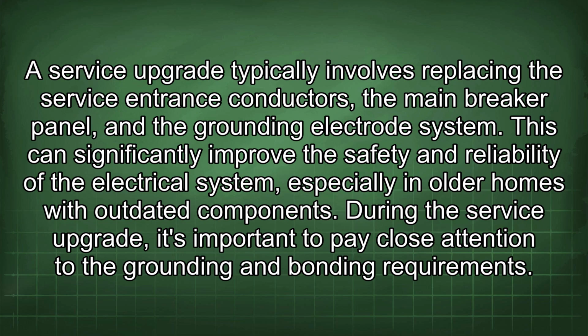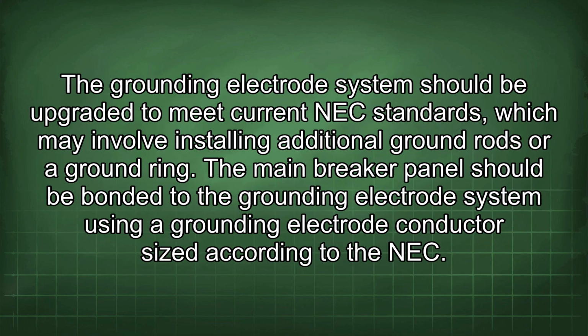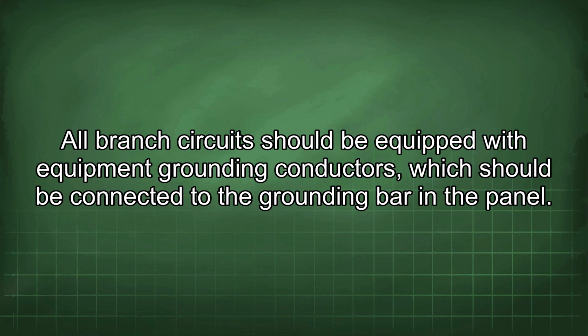During the service upgrade, it's important to pay close attention to the grounding and bonding requirements. The grounding electrode system should be upgraded to meet current NEC standards, which may involve installing additional ground rods or a ground ring. The main breaker panel should be bonded to the grounding electrode system using a grounding electrode conductor sized according to the NEC. All branch circuits should be equipped with equipment grounding conductors, which should be connected to the grounding bar in the panel.